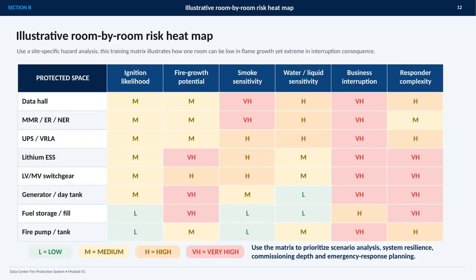This slide presents an illustrative, room-by-room risk heat map for a data center fire protection system. The key point is that risk is multidimensional. The matrix evaluates each protected space across ignition likelihood, fire growth potential, smoke sensitivity, water or liquid sensitivity, business interruption, and responder complexity. A room can have relatively modest fire growth potential, yet an extreme consequence if an incident interrupts critical operations. The rows cover spaces including the data hall, MMR, ER and NER rooms, UPS and VRLA areas, lithium energy storage, switchgear, generators, fuel storage, and fire pump facilities.